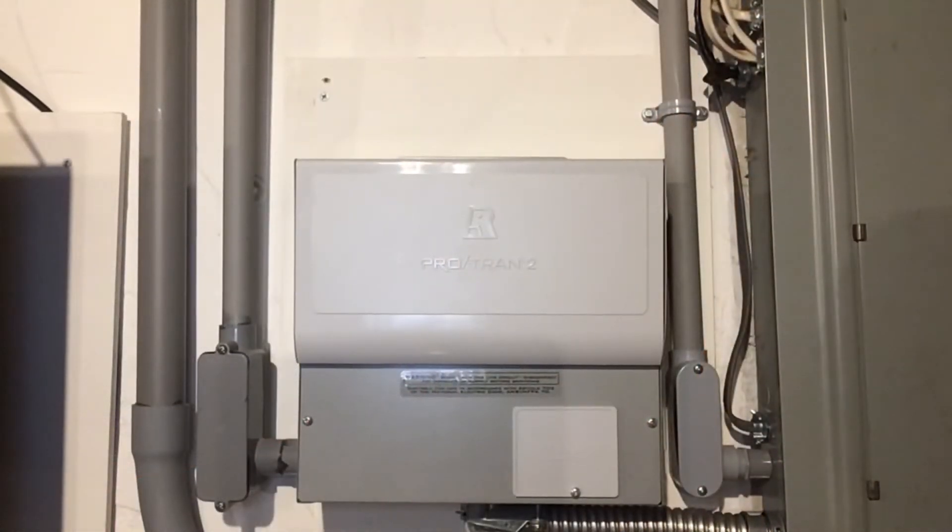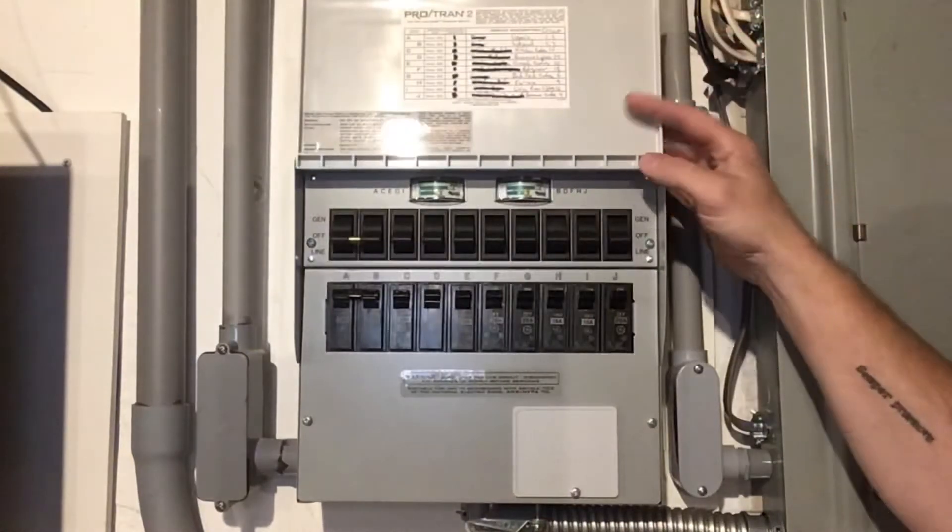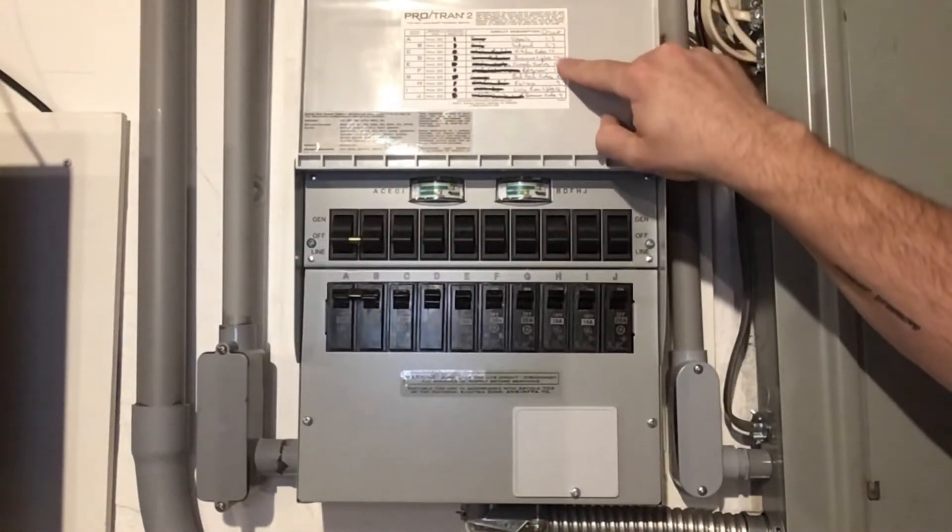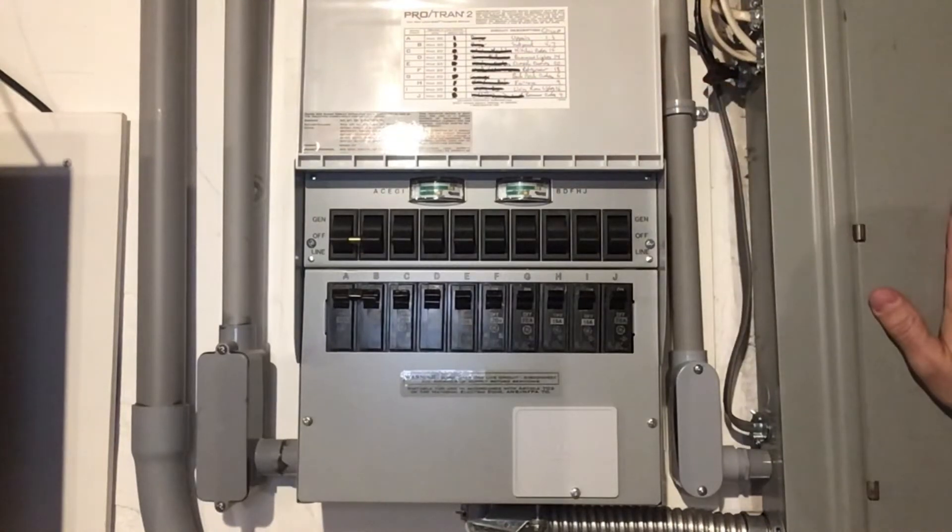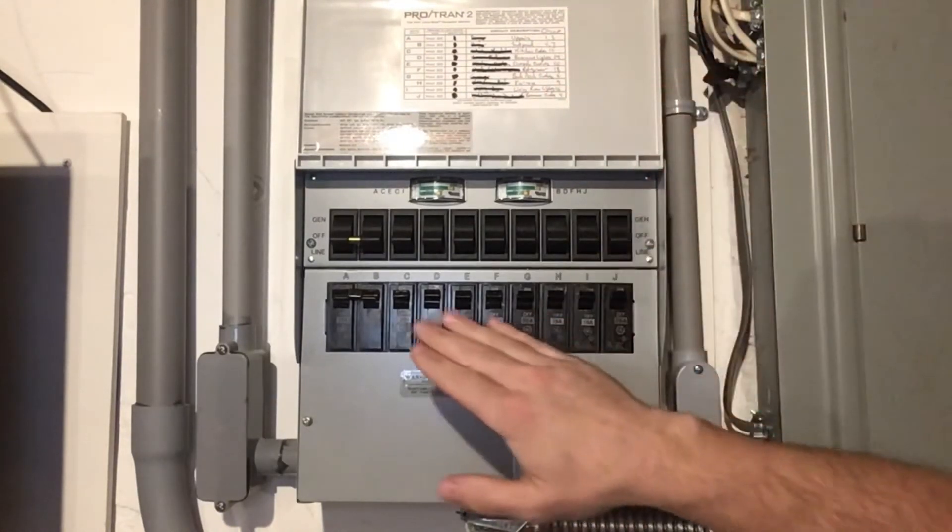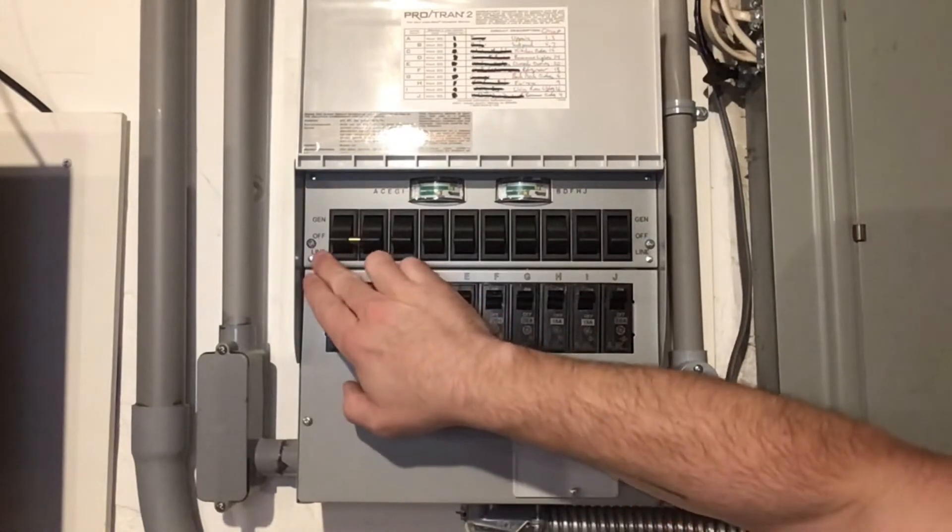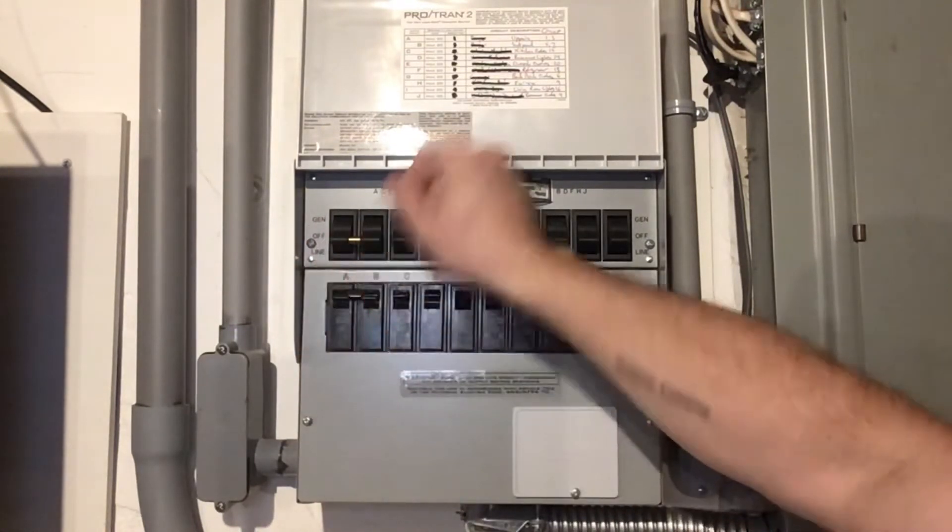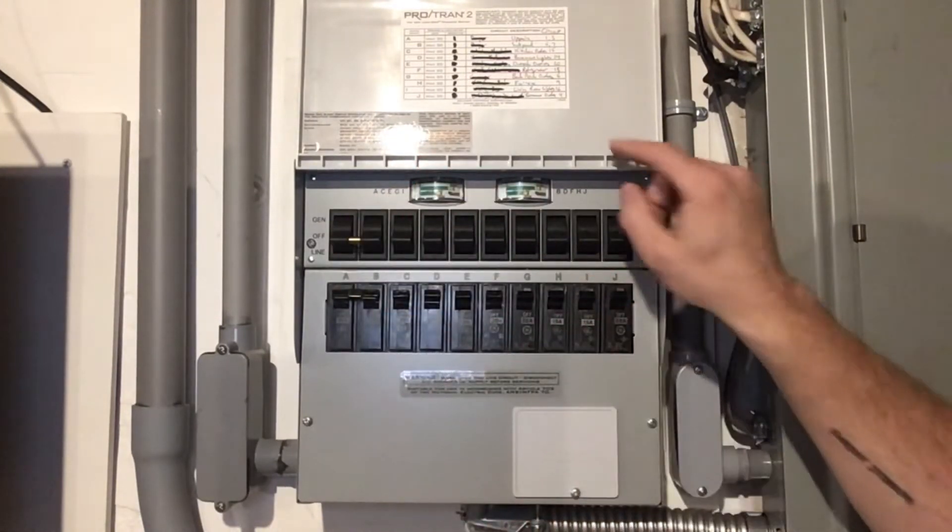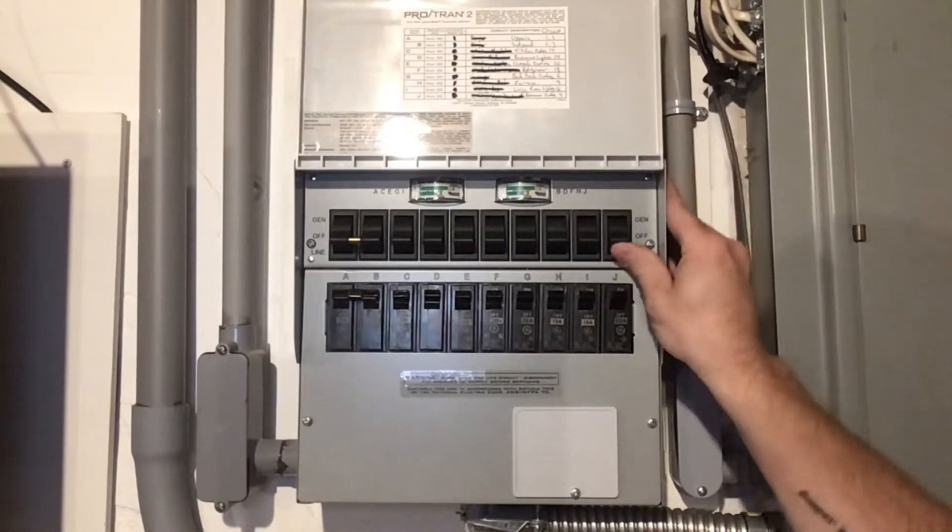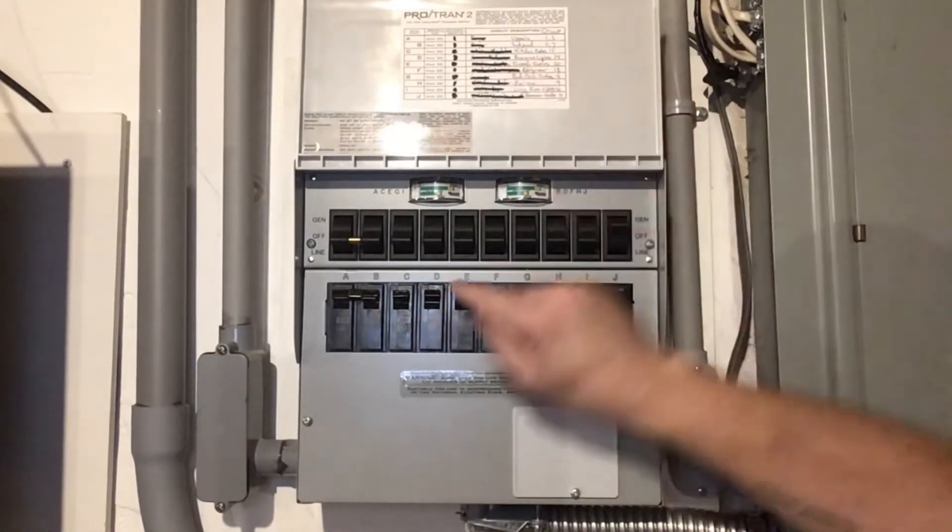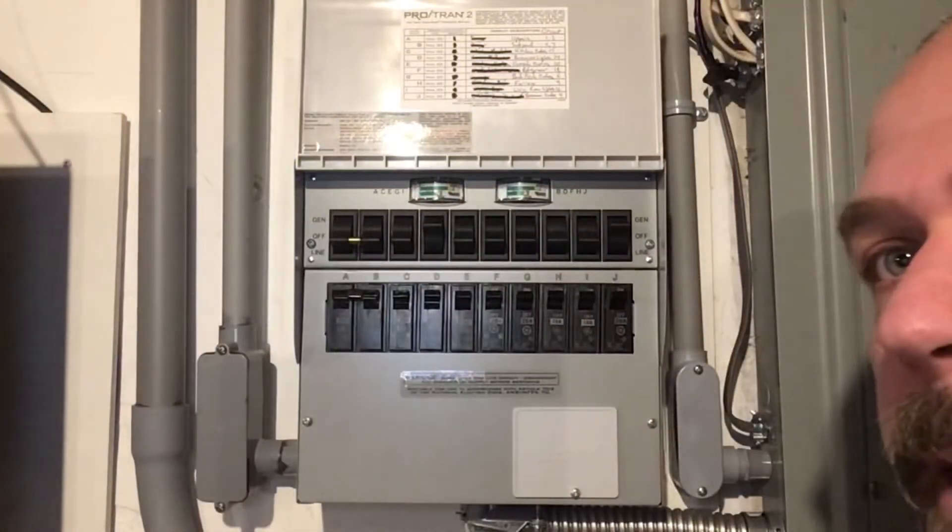With the generator running, we can come down to the panel. This is our transfer switch panel. Up top here, you can see I have all the circuits numbered to match what's in the main panel over here as well as named. To switch them from line, which is the power coming in, to gen, we take the switch, flip it up all the way. In the middle is off. That disconnects the circuit entirely. So let's see here. Let's do basement outlets. And let's do basement lights. Just like that.